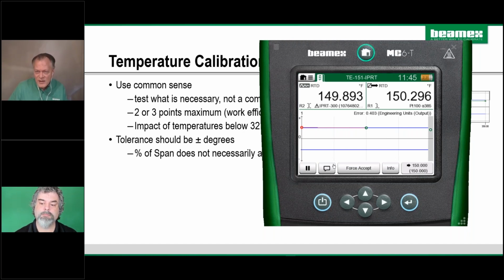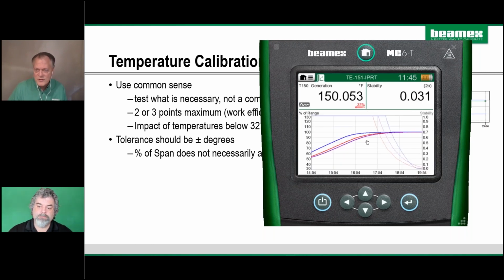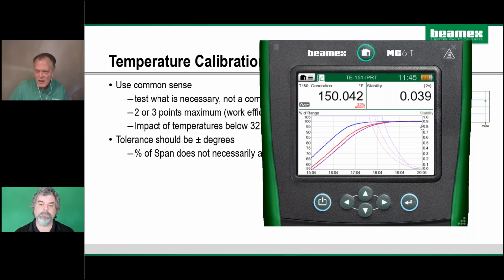And you can see now that the stability's kicking in, these guys have slowed down. It's a straight zero shift on this temperature probe. And let's take a look at it. So now our stability has gotten down very, I mean, we really could almost take a reading here. It's dwelling an extra minute or so here. And it looks like the internal reference is starting to come in. When that drops in, it's going to take a reading.